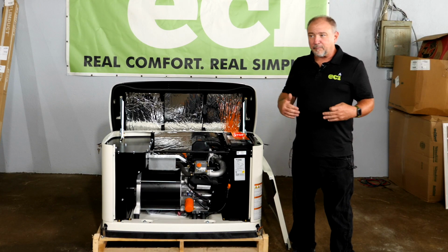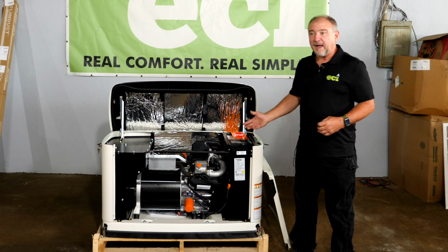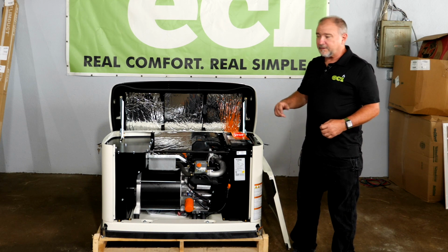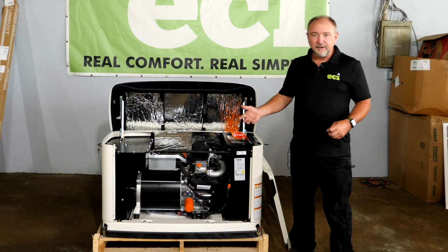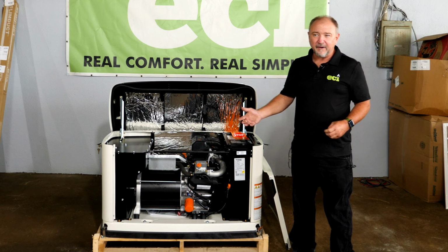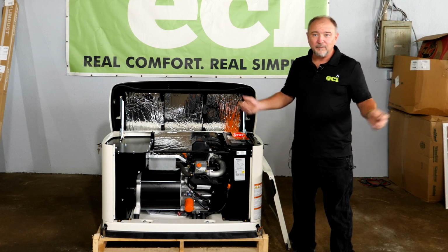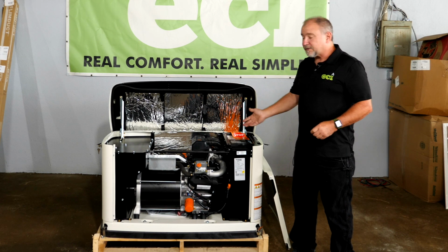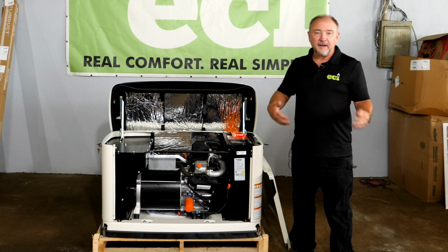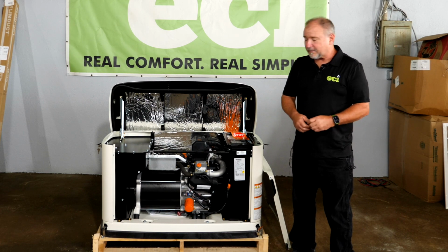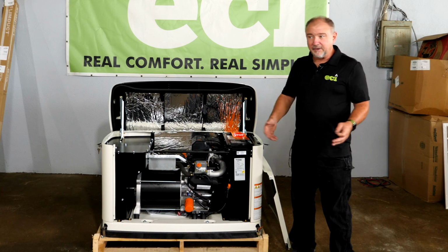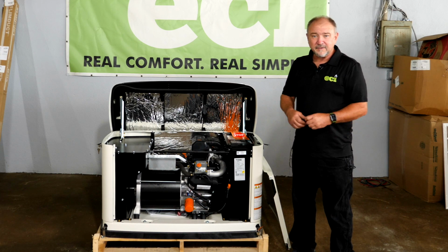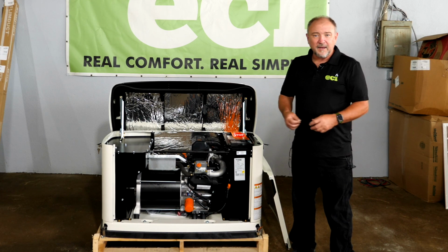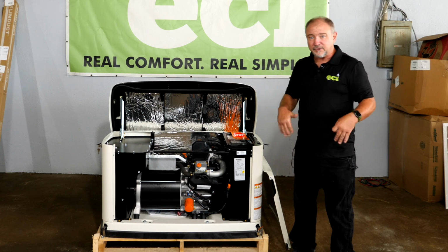During normal operation, we set this to exercise once a week or every other week—say, a predetermined day and time like Wednesday at 1 p.m. The generator will kick on to run an exercise cycle, making sure everything works as it should. It runs for a couple minutes to warm up the engine and confirm everything's good, then shuts down.